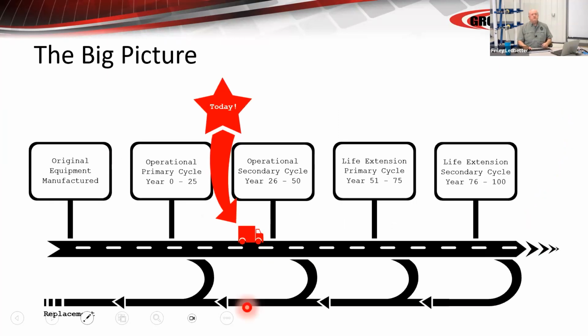So the big picture is, and this is a review of module 1, the equipment is designed to operate about 20 years. At that point, the manufacturer, sales team, and marketing team built in some planned obsolescence to get it away from you because they want to sell you new equipment, okay? That can't really happen because the cables and the operating conditions, as far as what gets built around the switchgear, won't allow you to get it out. So there are all kinds of operating conditions that go into this site-specific, maintenance-specific, operation-specific equipment, to where you can't necessarily go in and easily change it out.